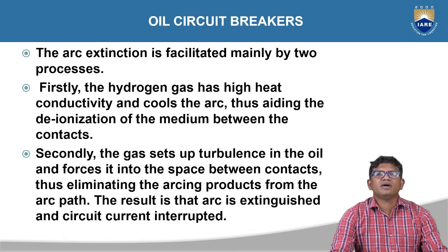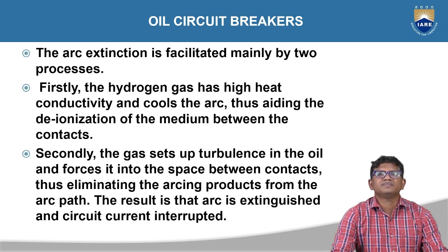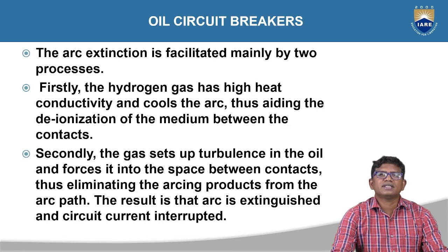The second process is that the gases set up turbulence in the oil. The oil flows around and between the contacts of the breaker, washing away the arcing particles. This causes deionization, builds sufficient dielectric strength between the contacts, and the arc extinction is facilitated.